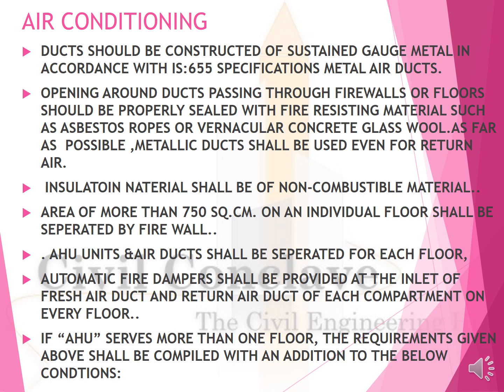Area of more than 750 square meter of an individual floor shall be separated by a firewall. AHU units and air ducts shall be separated for each floor. Automatic fire dampers shall be provided at the inlet of the fresh air duct and return air duct of each compartment on every floor. If AHU serves more than one floor, the requirements given above shall be complied with, in addition to the below condition.